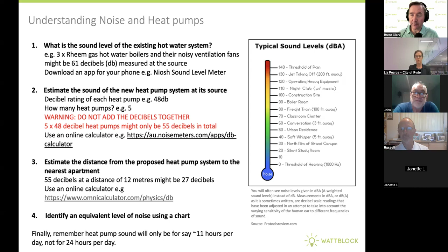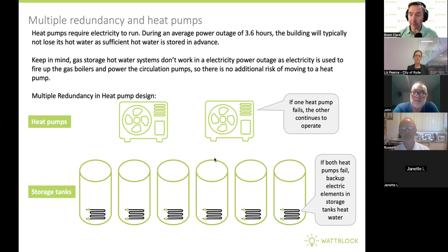Now, it is possible to design heat pump systems that have multiple redundancy. Keep in mind, the average power outage is usually 3.6 hours. Some of these heat pumps actually have more hot water storage than older gas storage hot water systems. And so you actually might sail through an average power outage without an impact on residents in an apartment building. And the other thing to keep in mind, if you've got an existing gas hot water plant for an apartment building, quite often you need electricity to fire the gas boilers. So when you have an electricity outage, your hot water system goes offline, even if you're on gas.